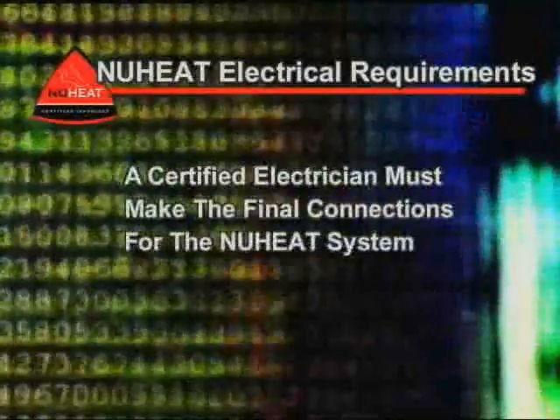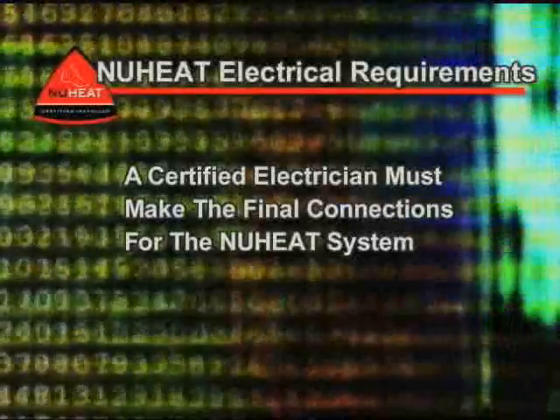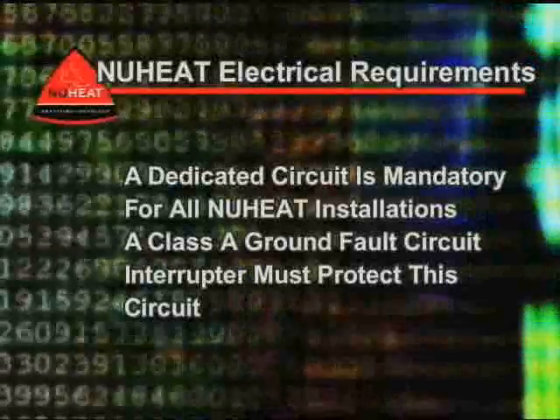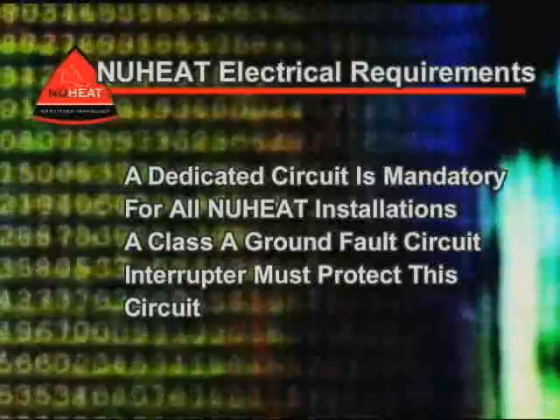1. A certified electrician must make the final connections for the NUHEAT system. 2. A dedicated circuit is mandatory for all NUHEAT installations. A Class A ground fault circuit interrupter must protect this circuit.